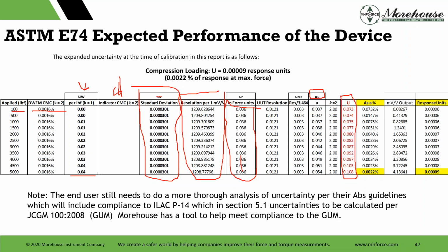And then if we wanted to take it as a percentage, what we do, we take this uncertainty and we divide by this number. So that 0.108 divided by 5,000 as a percentage, 0.002. We report that on our certificate here too. 0.002% of max response. And if you look at this compression loading, it says U equals 0.00009 response units. That's over here. So there we go.